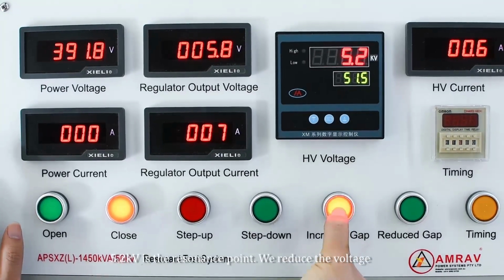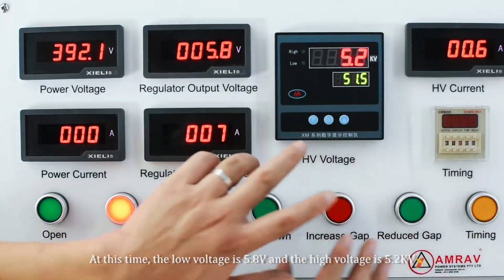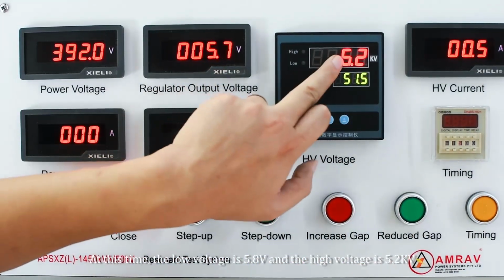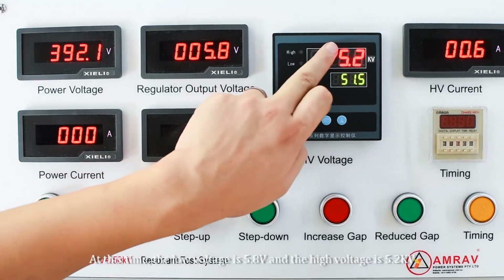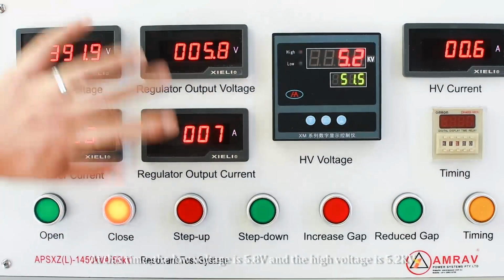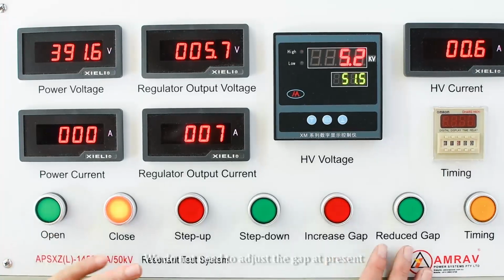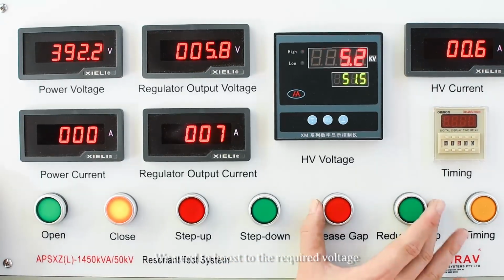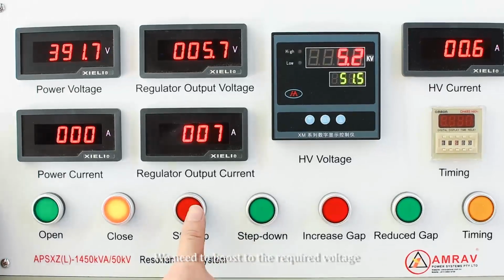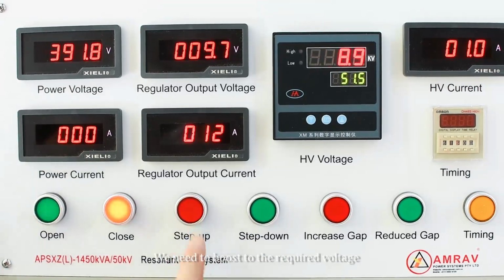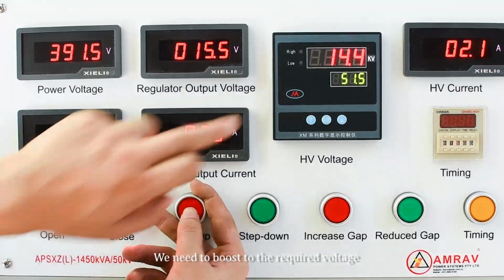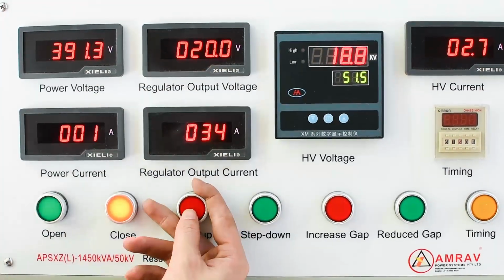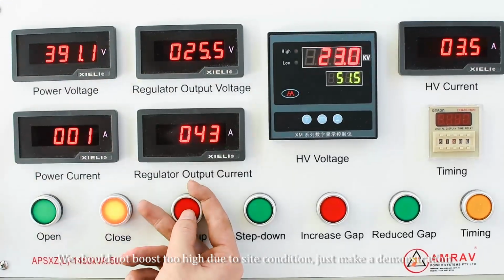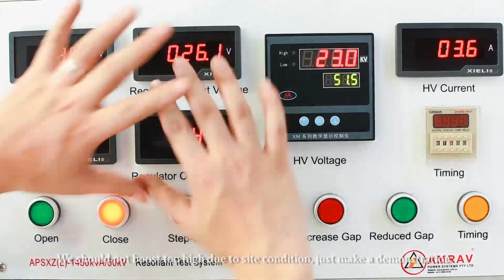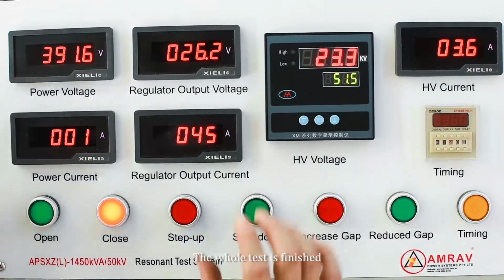We reduce the voltage. At this time, the low voltage is 5.8 volt and the high voltage is 5.2 kV. We don't need to adjust the gap at present. We need to boost to the required voltage. We should not boost too high due to the site condition. Just make a demonstration. The whole test is finished.